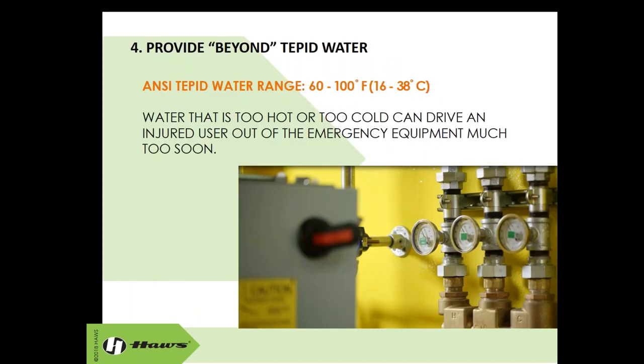Now, I want to suggest providing beyond tepid water. The ANSI tepid water range is 60 degrees Fahrenheit to 100 degrees Fahrenheit, right? But 60 degrees, I don't know if you've ever jumped in 60 degree water and hung out in there for 15 minutes, it's cold. It's not going to feel the best. And 100 degrees Fahrenheit, if you're sticking your eyeballs in it, is not going to feel great.